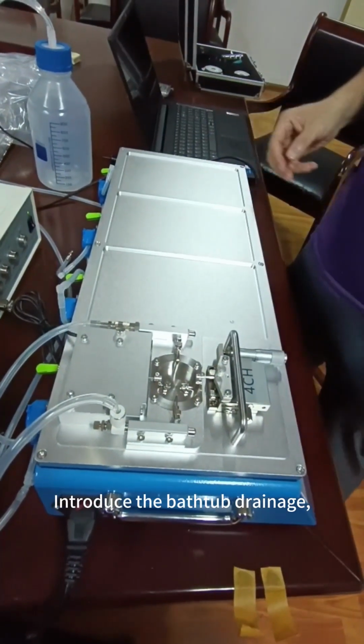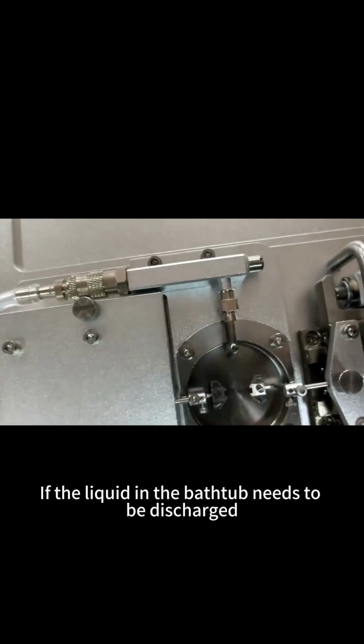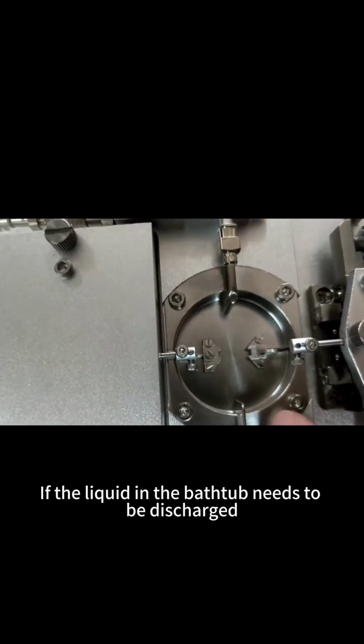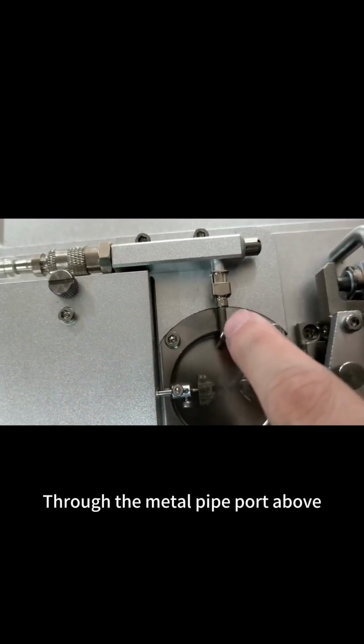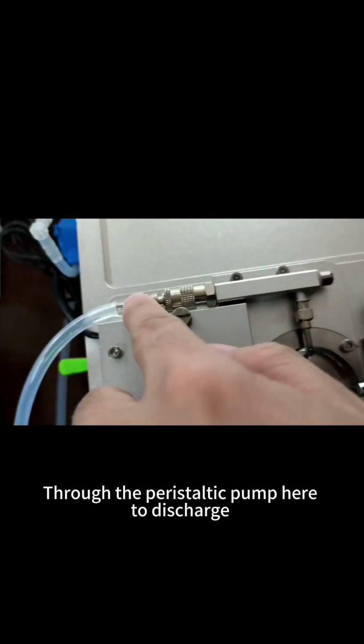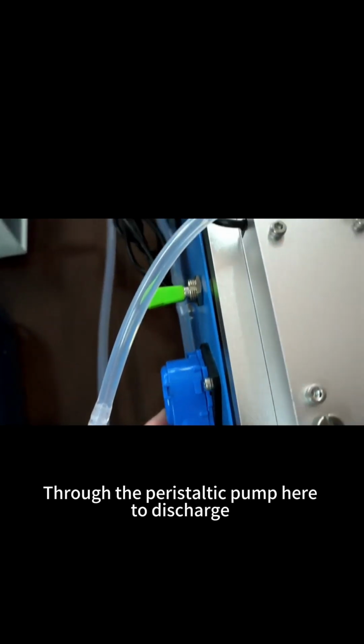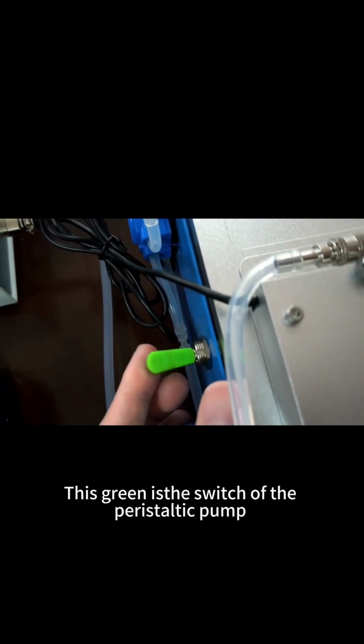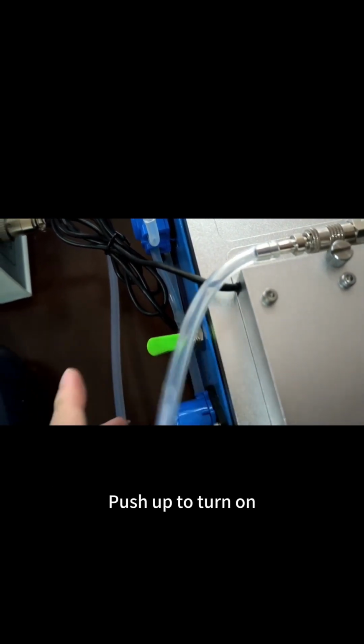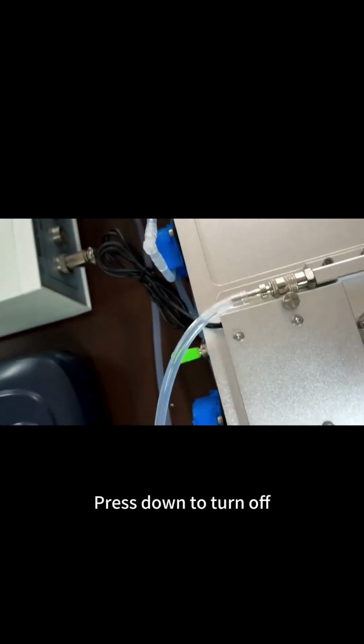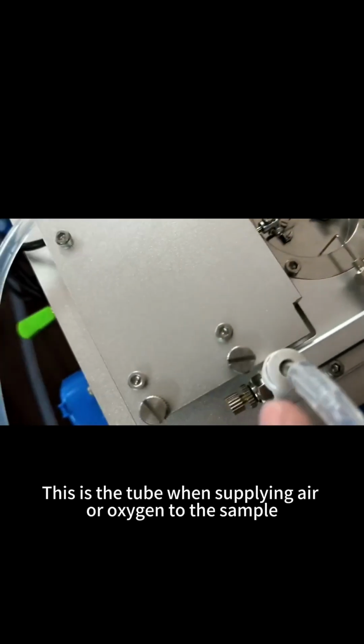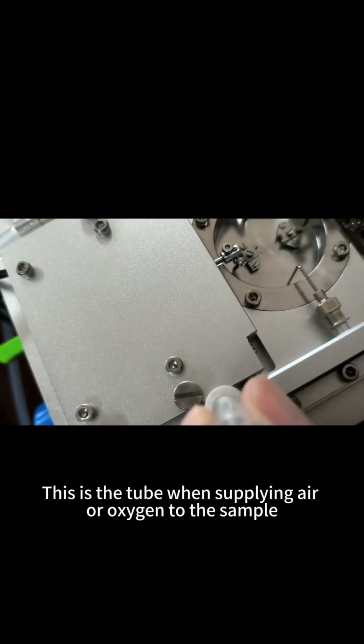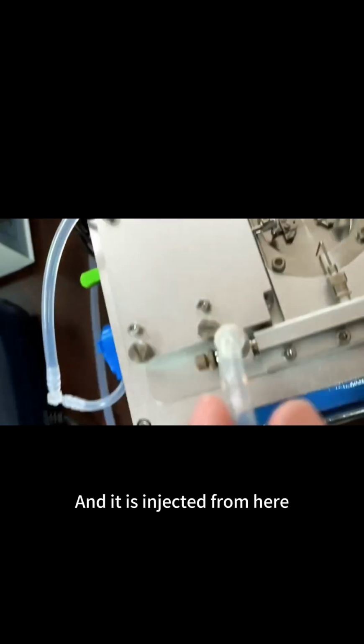Introduce the bathtub drainage: if the liquid in the bathtub needs to be discharged, it goes through the metal pipe port above, and then through the peristaltic pump here to discharge. This green is the switch of the peristaltic pump. Push up to turn on, press down to turn off. This is the tube when supplying air or oxygen to the sample, and it is injected from here.